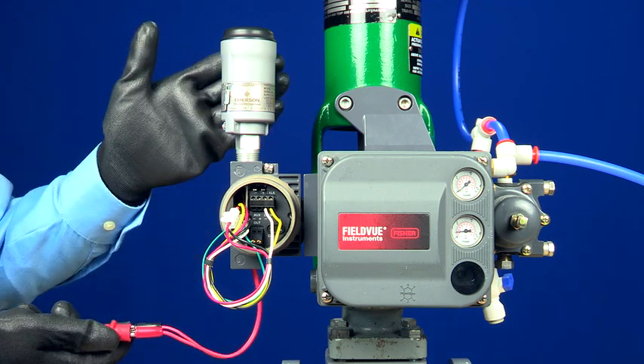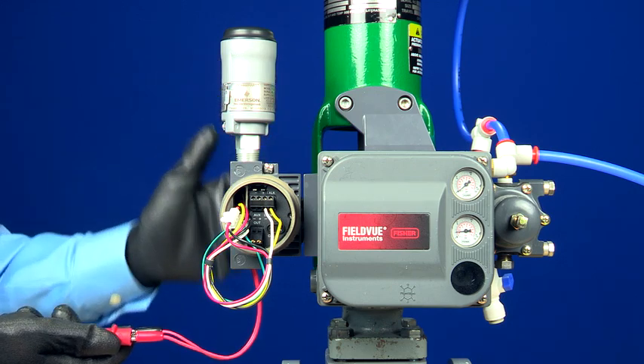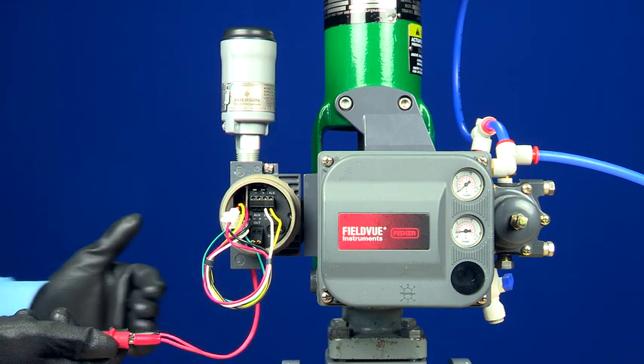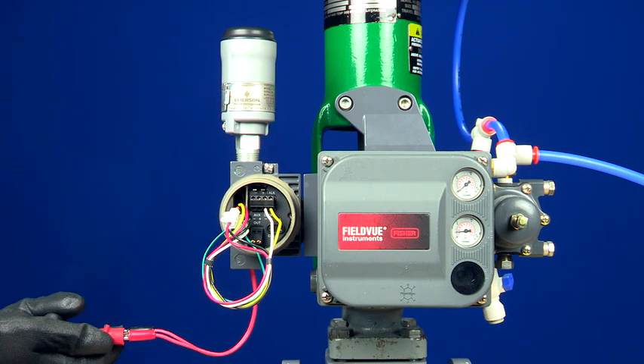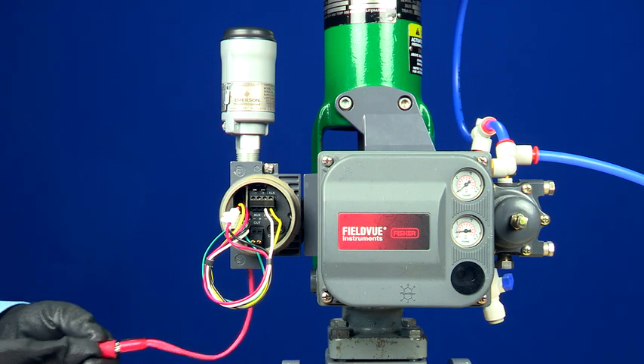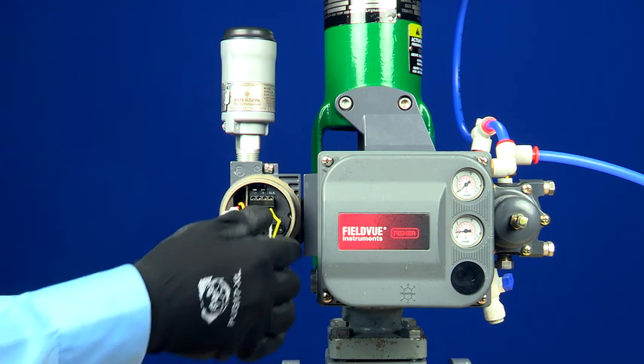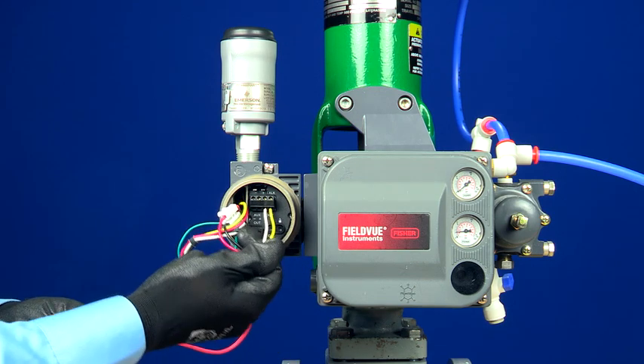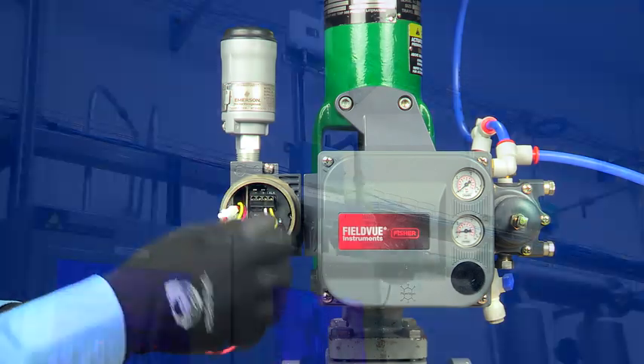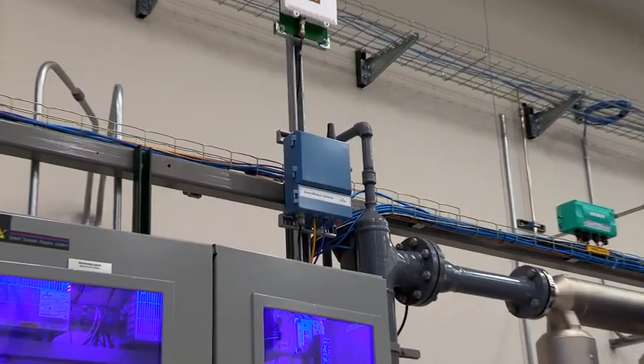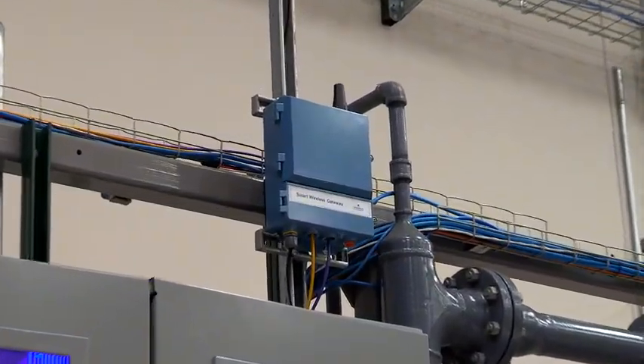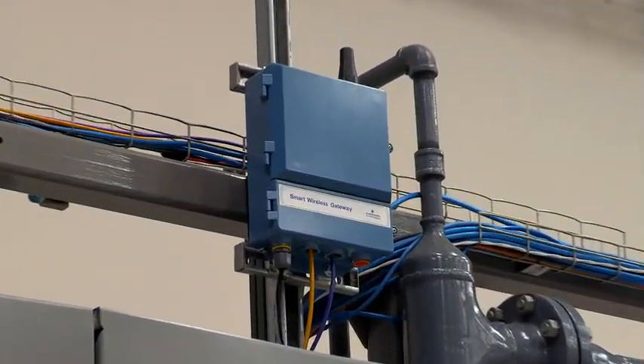The THUM adapter is loop powered and can be connected anywhere along the pair of wires running to the device. It then converts the HART information typically sent over these wires to a wireless HART signal that's received by a gateway. The information can then be viewed on a server or PC with AMS Device Manager.